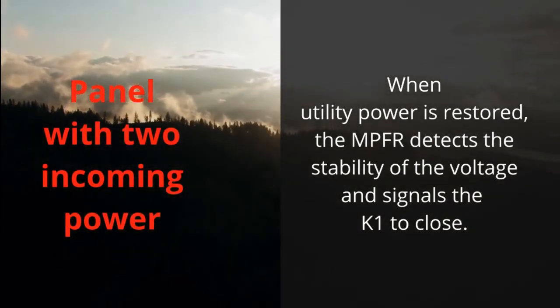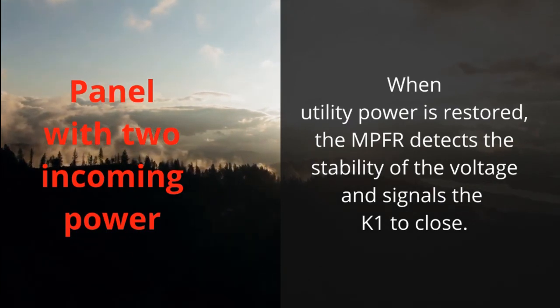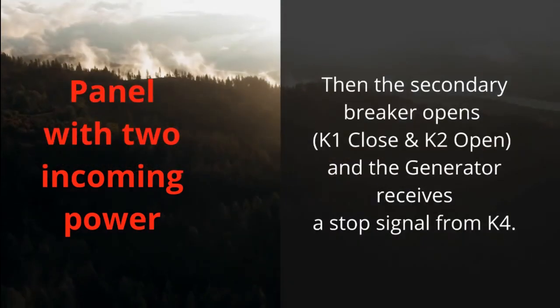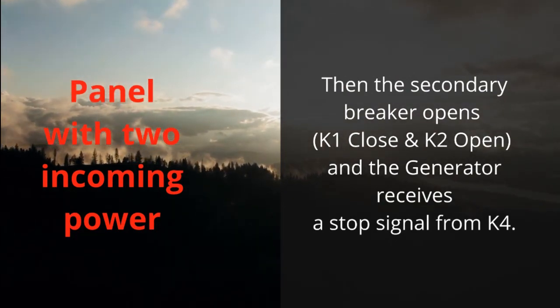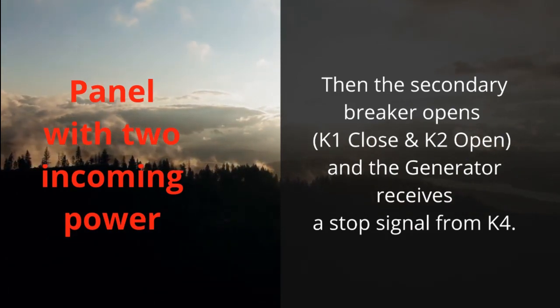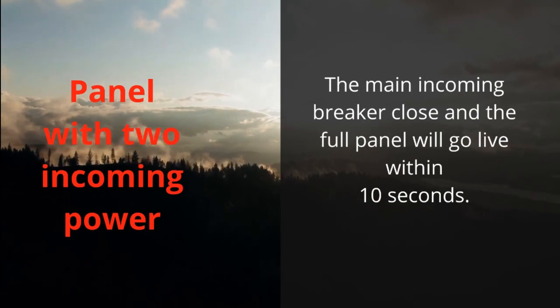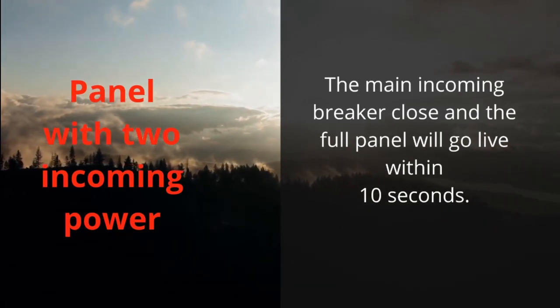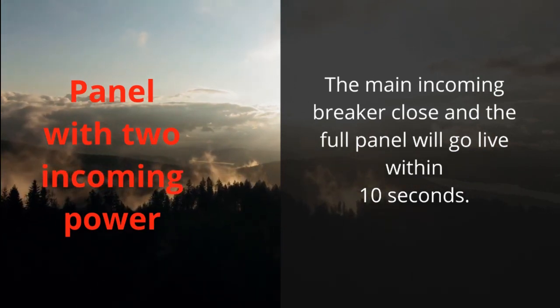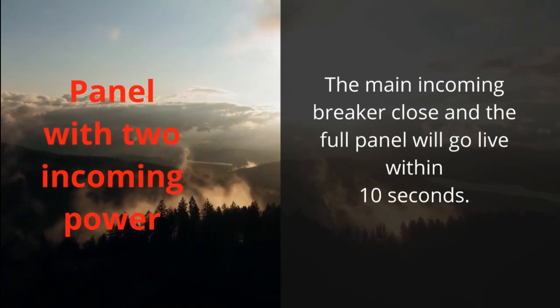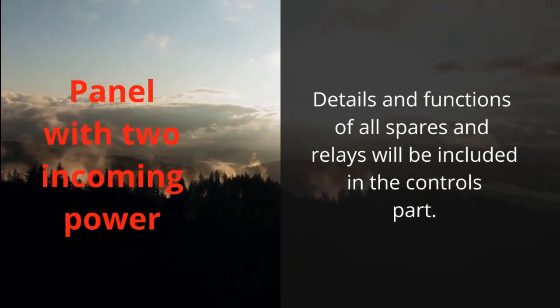When utility power is restored, the MPFR detects the stability of the voltage and signals K1 to close. Then the secondary breaker opens and the generator receives a stop signal from K4. The main incoming breaker closes and the full panel will go live within 10 seconds. Details and functions of all spares and relays will be included in the controls part.